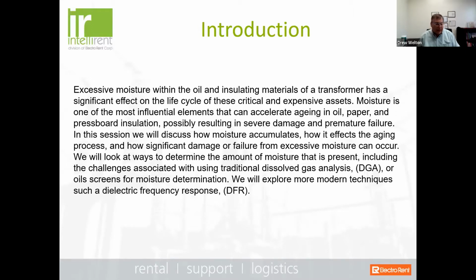So one of the things that we have to ask ourselves is what can we do to help protect our assets? There's a number of things we can do. We can certainly make sure that our protective relaying is in place to account for any transients that may come and cause mechanical damage to the transformer itself. But what I'd like to talk to you about today is excessive moisture. Two things that we know can greatly affect the life cycle of a transformer and its insulation are excessive moisture and heat.